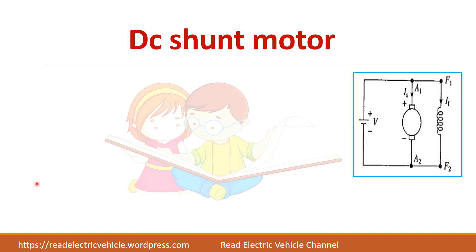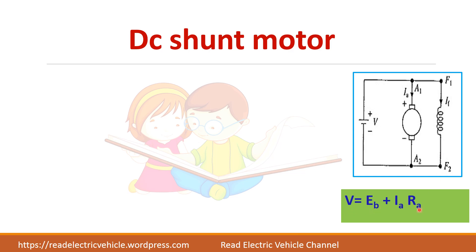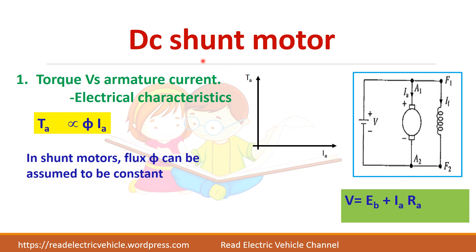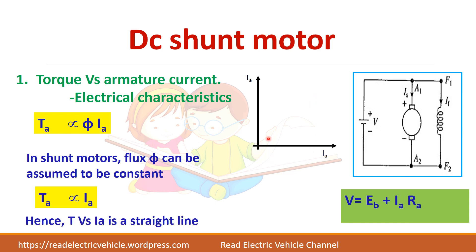Now let us see the characteristics for the DC shunt motor, where the field winding is connected in parallel with the armature. For the first characteristic — torque versus armature current — torque is directly proportional to flux times Ia. Since this is a shunt motor, flux is almost constant, so torque ∝ Ia. This gives a straight line. The shaft torque will be slightly less than the armature torque due to losses.